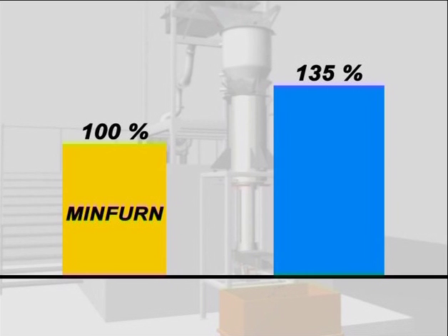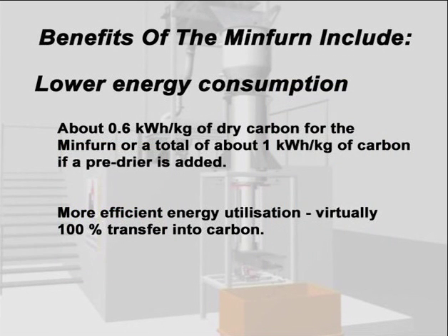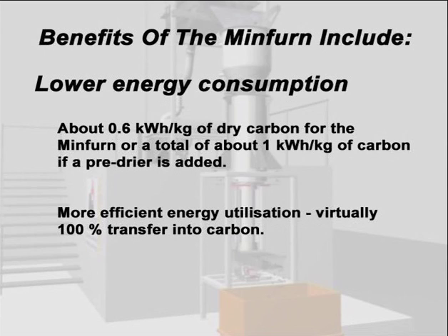Benefits of the Minfurn include lower energy consumption — about 0.6 kilowatt hour per kilogram of dry carbon for the Minfurn, or a total of about 1 kilowatt hour per kilogram of carbon if a pre-dryer is added — and more efficient energy utilization, with virtually 100% transfer into carbon.